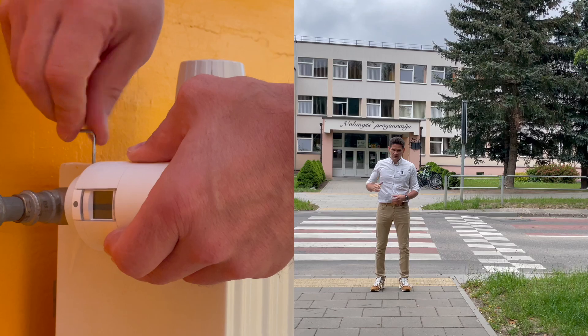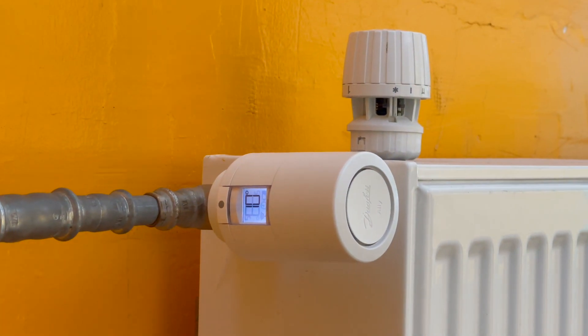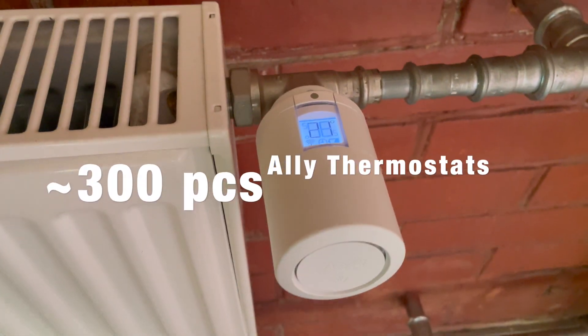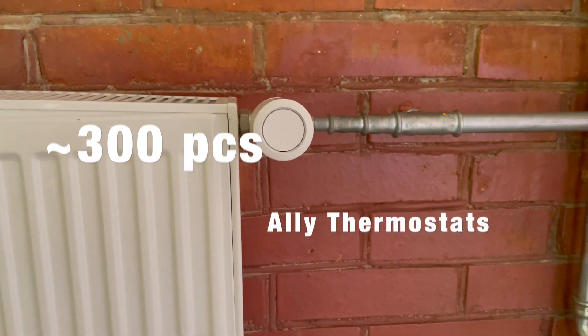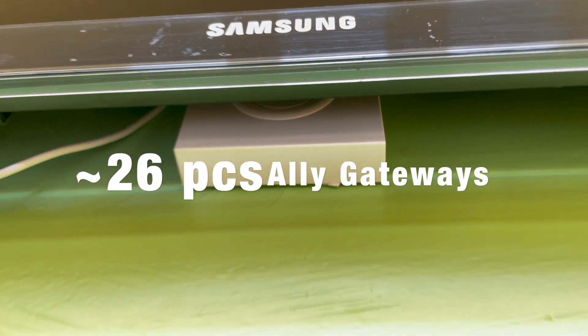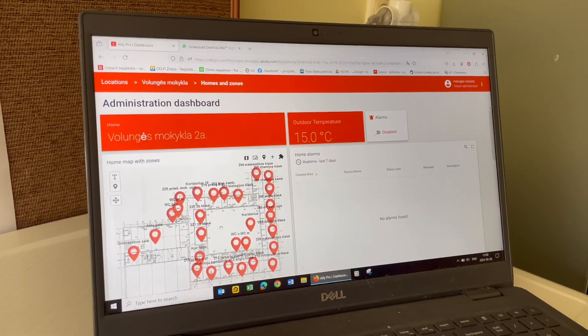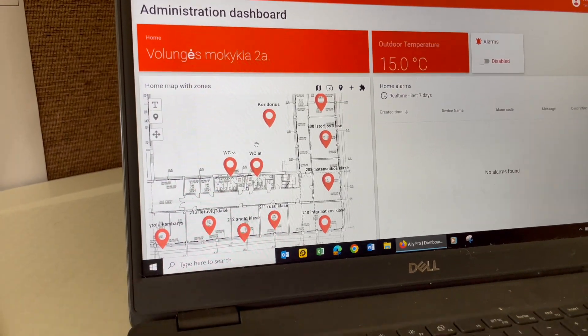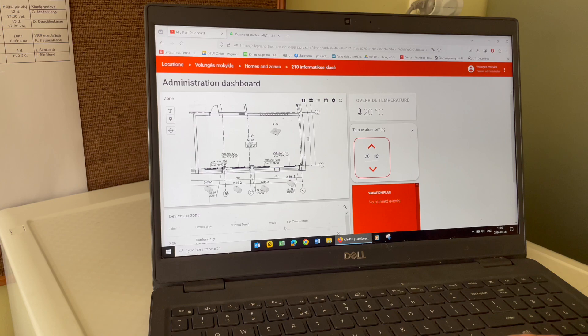In total, this secondary school is equipped with nearly 300 radiators — so nearly 300 smart electronic radiator thermostats — and around 26 Ally gateways. The gateways make a connection to the radiator thermostats, then go to the internet, and you can regulate everything from your tablet or computer.